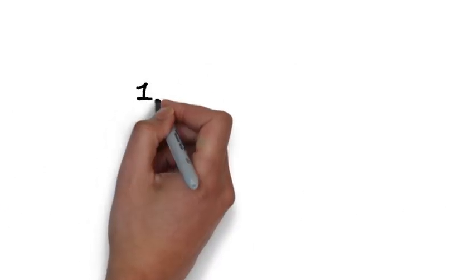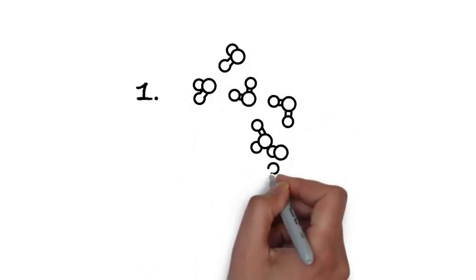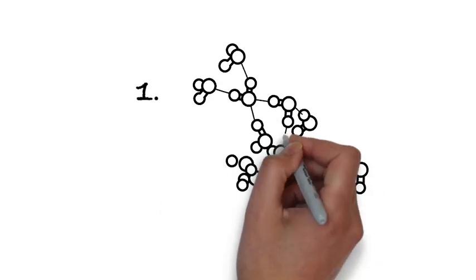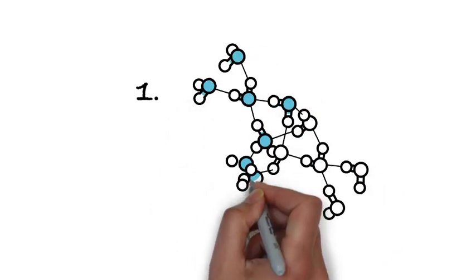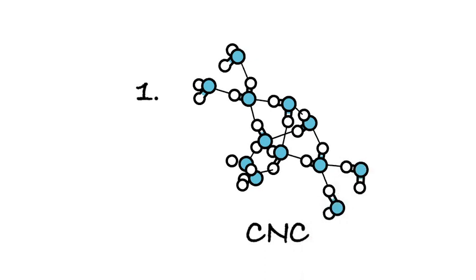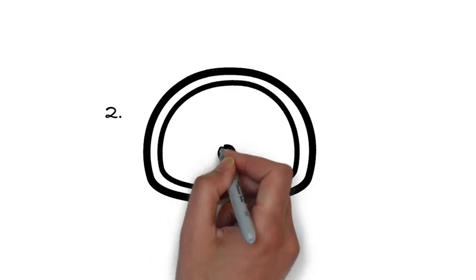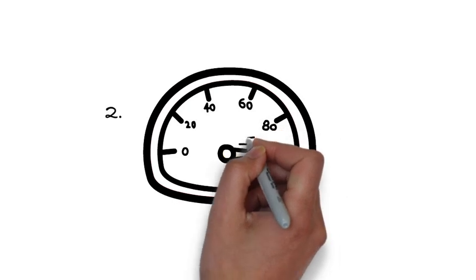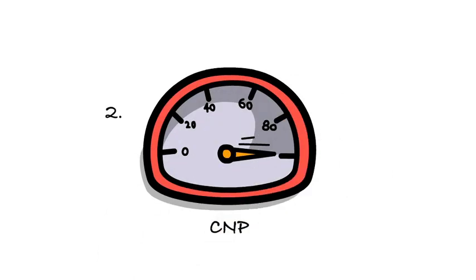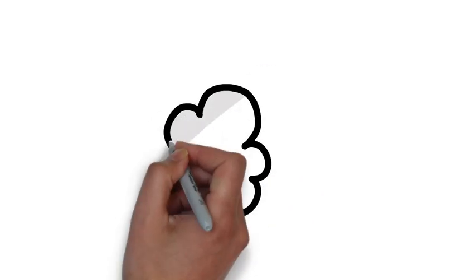First, the most widely used method is the ambient aerosol method using condensation nuclei counting, CNC, which can best be described as challenging the seal of the respirator with naturally occurring ultrafine particulates, which mimic gas molecules due to their extremely low mass characteristics. And secondly, the controlled negative pressure, or CNP, method, which pulls a slight negative pressure inside the mask and then measures the exhaust to determine how much more air must be pumped out in order to maintain that same low pressure.